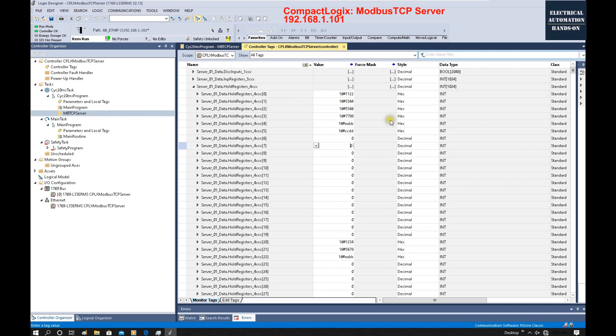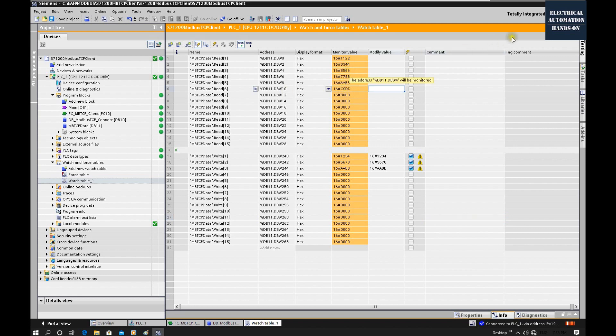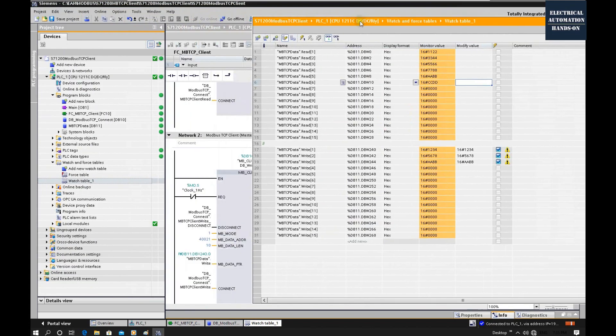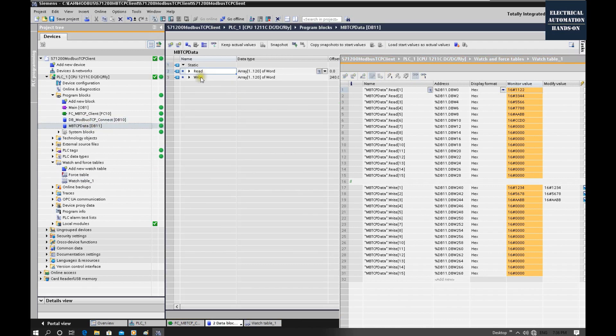We prepared the data on the server side. The first Siemens function block reads data from Modbus TCP address 40,001 to 40,010 — reading from the server to the client. Let's verify on the Siemens side. After switching back, we can see 0x1122, 0x3344, and all the other data transferred correctly. For the read function block, the Modbus address starts at 40,001 with length 10. The read buffer in DB11 starts at index 1, so the index number matches the Modbus address with no one-address offset issue.